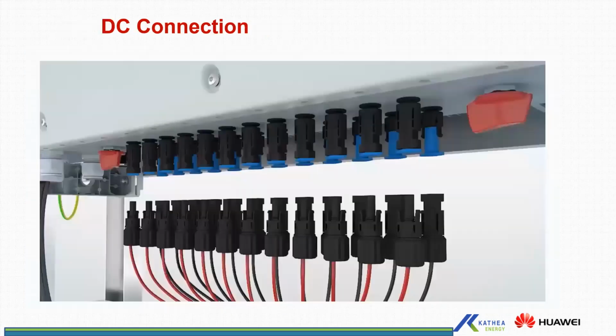And then the DC connections. The inverter has built-in MC4 connectors underneath for all the string channels. The inverter has built-in SPD and DC switches, so some installers would prefer not to have external protection for their strings. You can actually wire your strings straight from the field to the inverter. You just need MC4 connectors to plug into the inverter. Preferably, you can install a fuse box between your strings and the inverter to be able to isolate your strings.